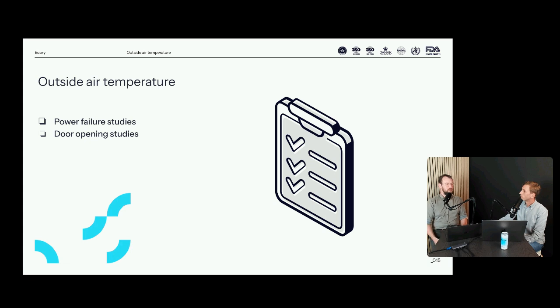We haven't seen companies avoid doing power failure studies or door opening studies just because outside temperatures were similar, because there's still potential risk of equipment heating up above outside air temperature. But it's something to be cautious about when doing a power failure or door opening study - sometimes it's just not possible to see any changes because the outside air temperatures happen to be within acceptable ranges. So that's one of the smaller, more amusing things - there are tests that really end up showing us nothing, which is actually a good outcome.